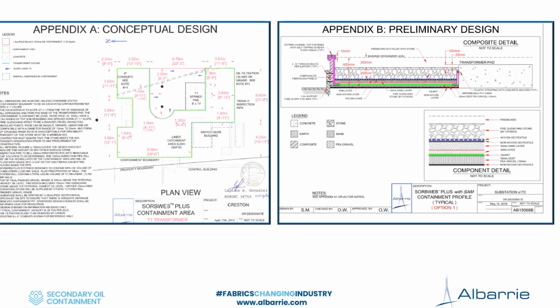Just to showcase the flexibility, we're not confined to any specific geometric shape. It doesn't have to be a square or rectangle. It can go around all kinds of different things. In this case, this is a substation on the side of a mountain. This transformer is over 100 years old, or was at the time, and has quite a lot of oil in it, as well as PCBs. So we built almost the entire substation as the containment, using a combination of shallow and deeper areas in order to contain that amount of liquid.